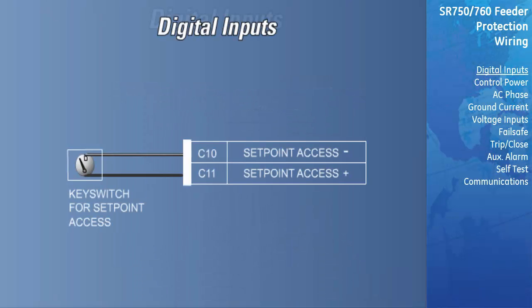There are a total of 14 digital inputs that are designed for dry or wet contact connection to other devices. One of the digital inputs, the setpoint access input, has its own common, while the rest of the inputs share commons. The setpoint access switch allows the front keypad to be used to program the relay. This can be wired as a dry contact connection only.